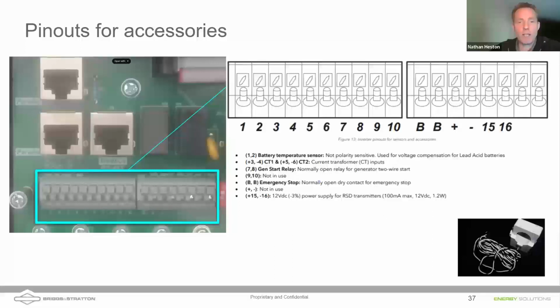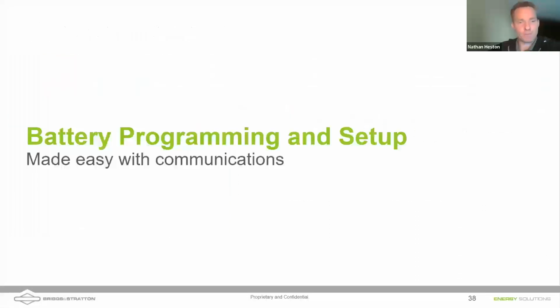The Gen Start relay, that's pins 7 and 8 on the Sol-Ark. And then the E-stop button, which is also important. That is a normally open dry contact. So you want to get a switch that's normally open. And then when you close it, it completes the circuit and does an E-stop. So that's the BB on the right side of the pinouts.